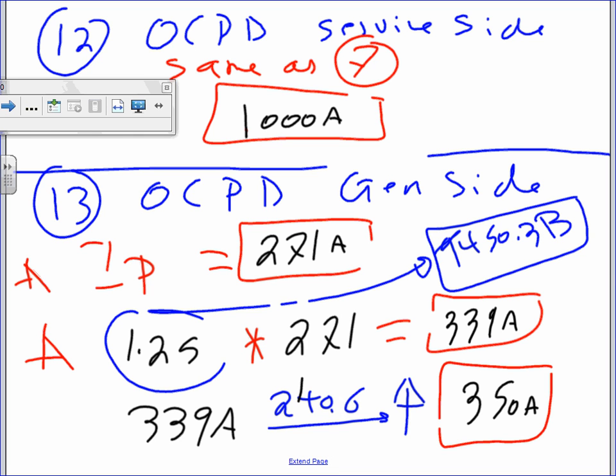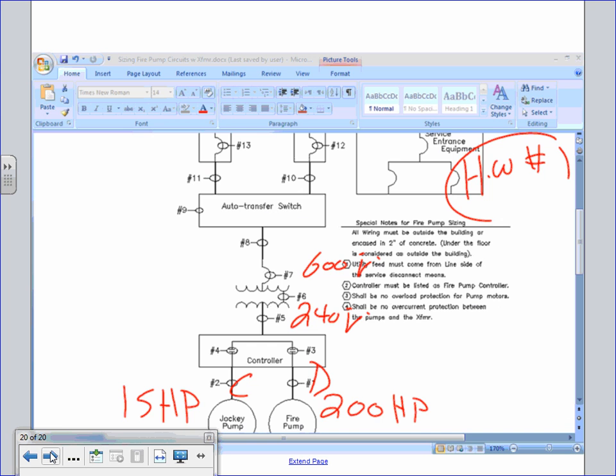Any comments, guys? Any questions? I'm going to show you the homework that goes with that one. That will be homework number 14, the last homework that you guys are going to do with your friend Chad. Here's your homework number 14. Now we have a 15 horsepower at 600. The primary voltage is 600. The secondary voltage, guys, is 240. And it's 200 horsepower, and you are to do the same calculation for your friend Chad.